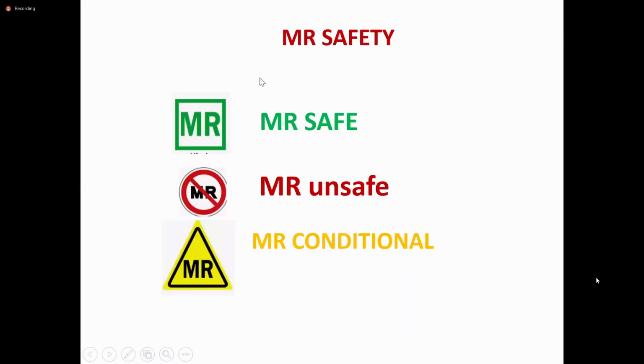Okay. So I'm concluding with a little bit of safety. All technologists should be aware of the signages: which are MR safe instruments or equipment that can be taken inside, and which are MR unsafe and have to be avoided and should not be taken inside. And there are some appliances that are MR conditional, that is, whenever necessity arises, you can go inside.